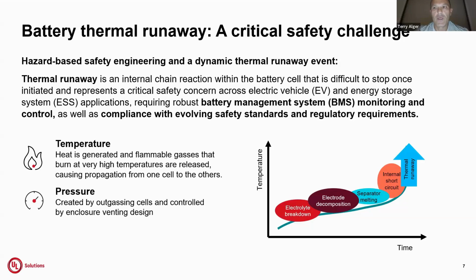The panelists before us talked a lot about BESS in data center applications, and thermal runaway in one of those data center applications would be quite concerning. Maybe not necessarily in terms of hazards to life, but definitely hazards to property and in the value lost if a data center were to ever catch fire. So what we need to do is make sure the battery management systems have very robust monitoring and controls in place, and that the battery system in general complies with the safety standards and regulatory requirements to keep people and property safe.